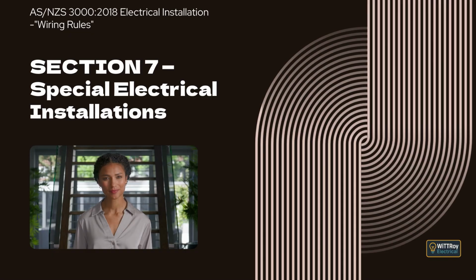Clause 7.5.12.2 Protection by SELV. This clause explains that, for SELV systems, separation of live parts from other circuits and from earth must be confirmed by measuring insulation resistance. Clause 7.5.12.3 Protection by PELV. This clause explains that, for PELV systems, separation of live parts from other circuits must also be confirmed by insulation resistance measurement.